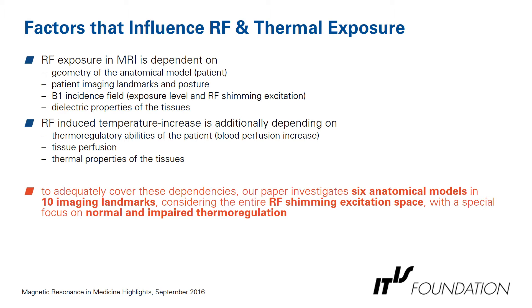The factors that influence RF and thermal exposures are the geometry of the anatomical model of the patient, the patient imaging landmark (whether it's head, heart, or leg imaging), and the patient posture. Also the B1 incident field — the exposure level — and the RF shimming excitation configuration, as well as the dielectric properties of the tissues. The RF-induced temperature increase additionally depends on the thermoregulatory abilities of the patient, especially the local blood perfusion increase, as well as tissue perfusion and thermal properties of the tissues.